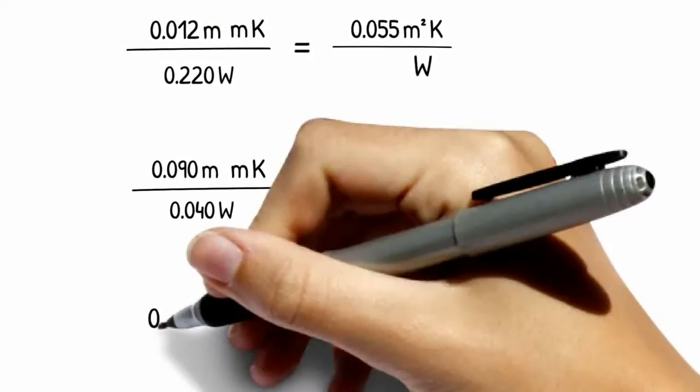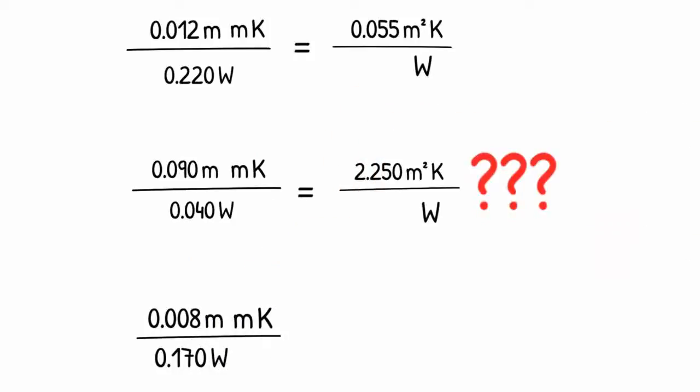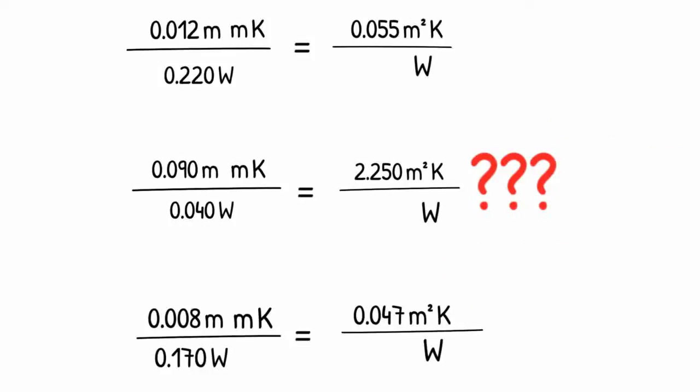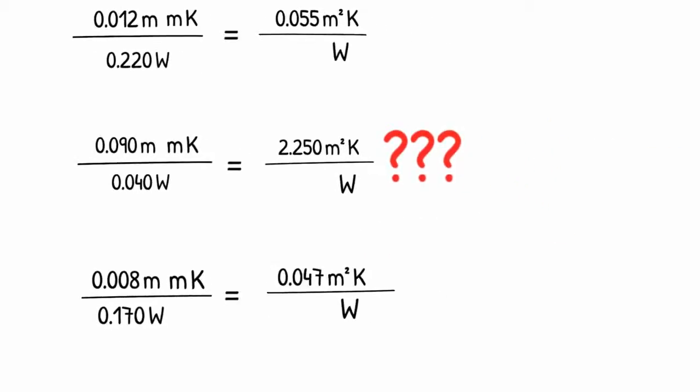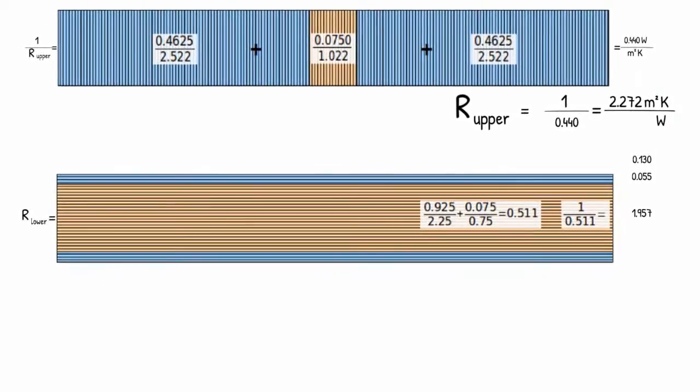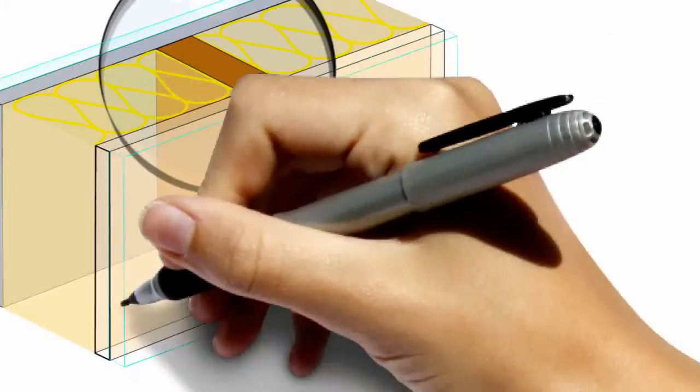We still need to calculate the resistance of the exterior plywood layer in the usual way by putting the layer thickness over thermal conductivity which gives us a resistance for this layer of 0.047 square meter times kelvin over watt and we need to transfer this to our summation here. Add exterior surface resistance which is lower due to it being windy on the outside.